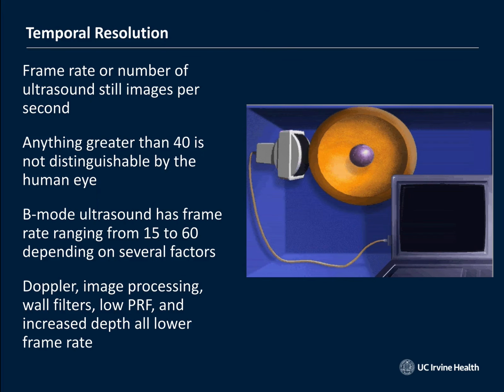The problem with Doppler, though, is that when you activate the Doppler, you've got two things going on now. You've got the B mode, and then on top of it, you've got the Doppler sampling. And so what that does is it crushes your temporal resolution. Temporal resolution is frame rate, the number of frames per second passing in front of your eye. On ultrasound, anything greater than 40 frames per second, you can't tell it's just a bunch of still images strung together. B mode ultrasound has really high frame rates when you're using cardiac software. When you activate the cardiology package on any ultrasound machine, those cardiologists want to see every possible range of motion that those sarcomeres are doing so that they can best assess ejection fraction, right? And so they love high frame rate.